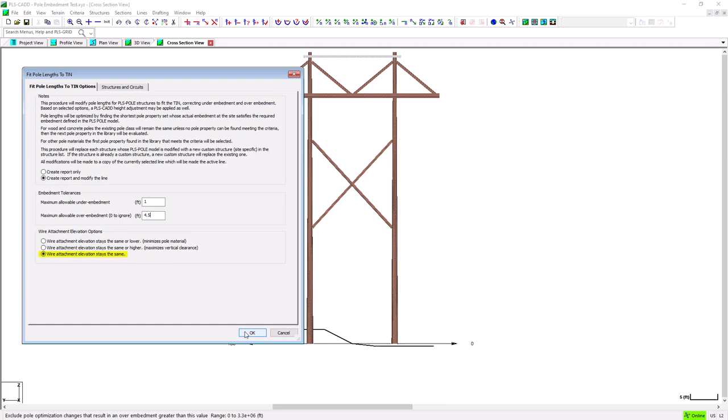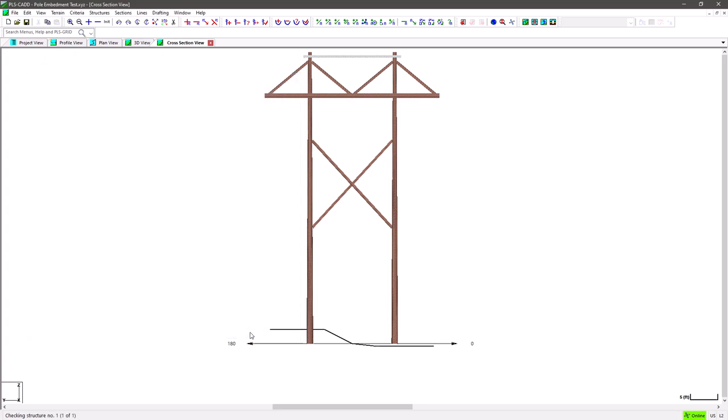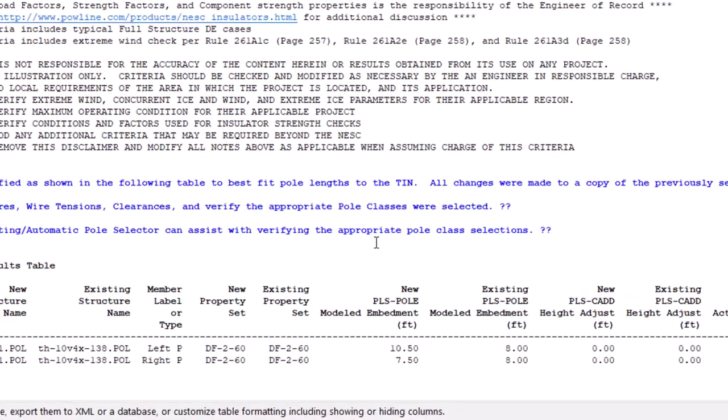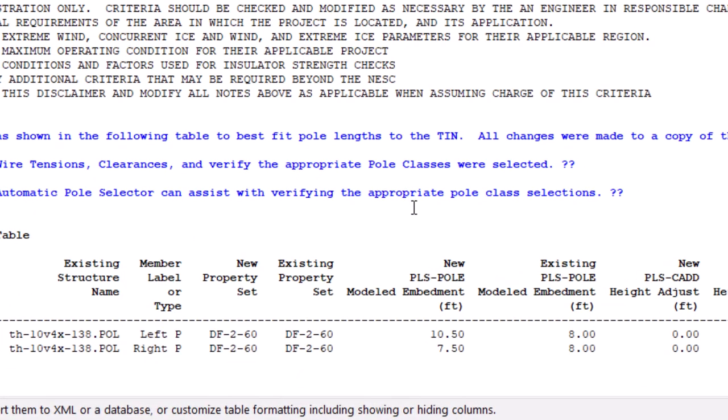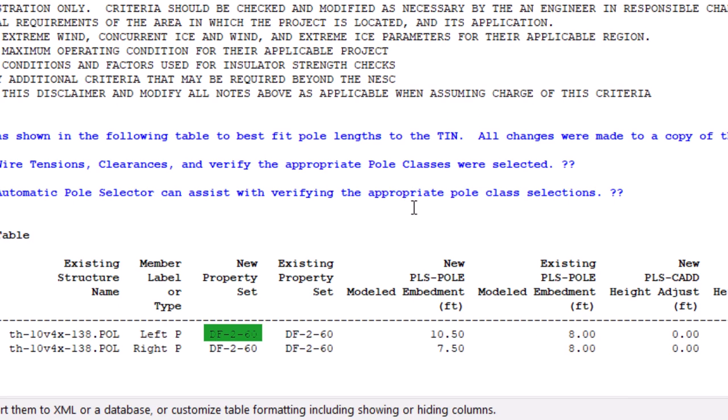We will leave this setting unchanged and keep the wires at the existing elevations. And when we look at the results now, we can see that because the right pole was only 0.5 feet above the tin, and it's less than the under embedment threshold, the program kept the pole length the same this time, but under embedded it by 0.5 feet. And the left pole, since it needed 2.5 feet of over embedment, and this was less than the threshold of 4.8 feet, it kept the pole length the same as well, and over embedded it by 2.5 feet.